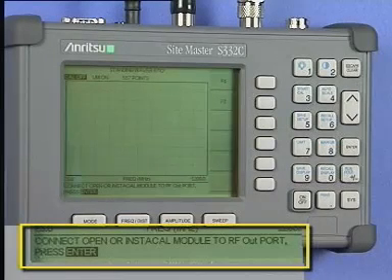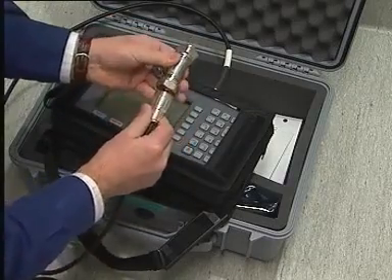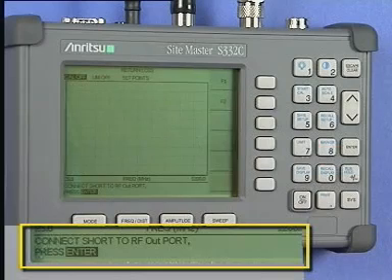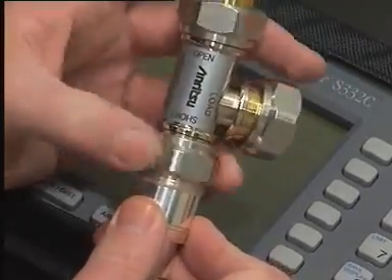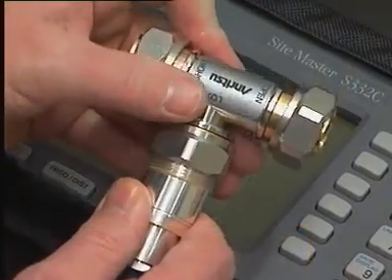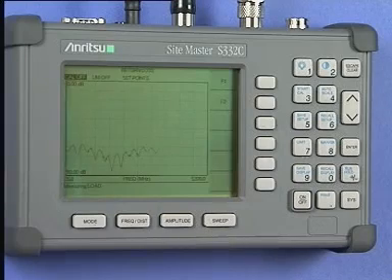At the bottom of the screen you will see the text Connect Open or InstaCal module to RF Out Port, which is asking you to connect the calibrated open circuit to the extension cable connected to the instrument. When you have done this, press the Enter key and the instrument will sweep and measure your chosen band of frequencies. After a few moments the Site Master will prompt you with the message Connect Short to RF Out, asking you to connect the calibrated short circuit to the extension cable. When you have done this, press the Enter key and the instrument will again sweep and measure. The Site Master will then prompt you with Connect Load to RF Out, asking you to connect the calibrated 50 Ohm dummy load. When you have done this, press the Enter key and the instrument will once again sweep and measure.